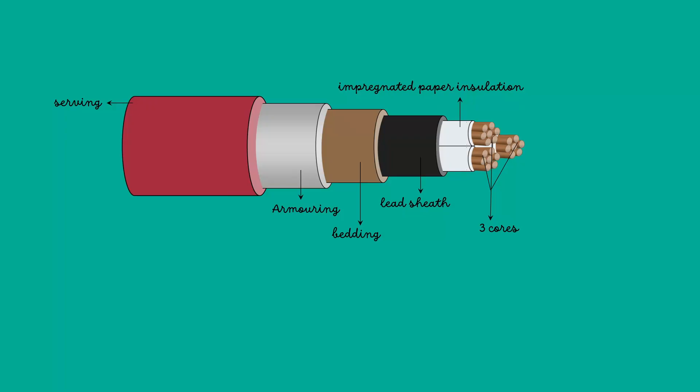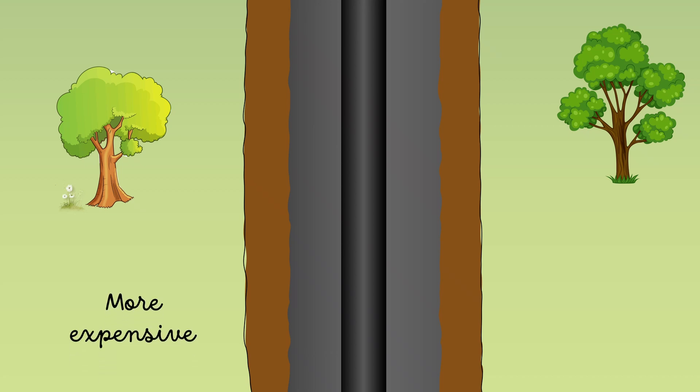Cables laid in this manner are usually plain lead covered because troughing offers good mechanical protection. This system is more expensive than the direct laying system. Due to poor heat dissipation facilities, the current carrying capacity of the cable is reduced.